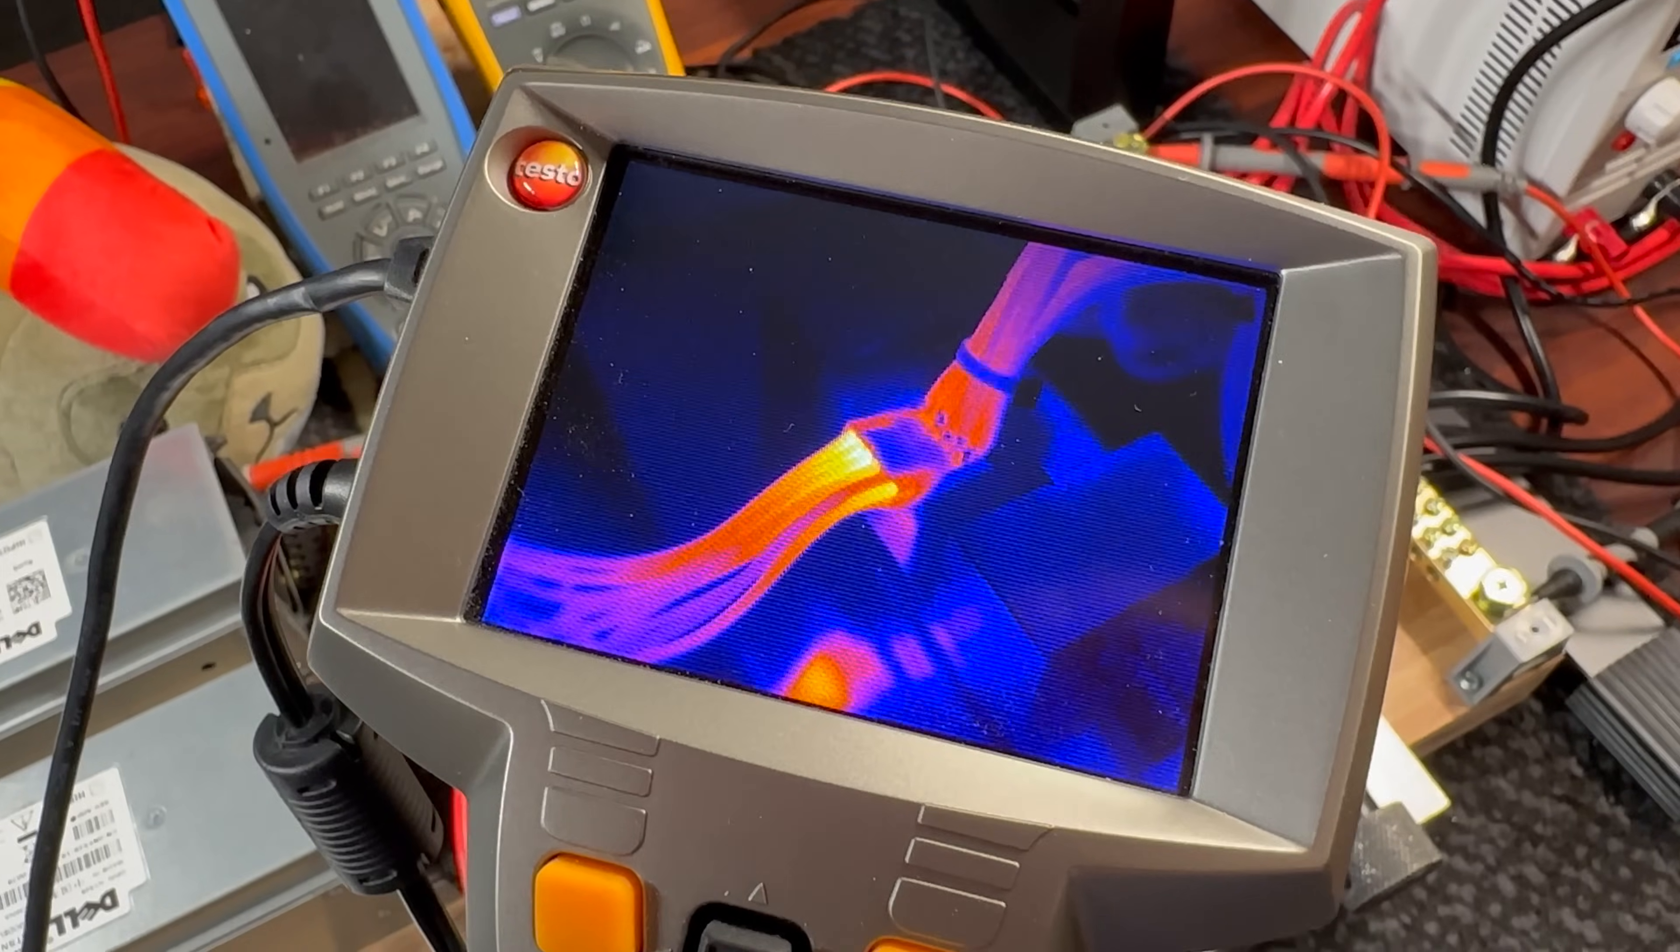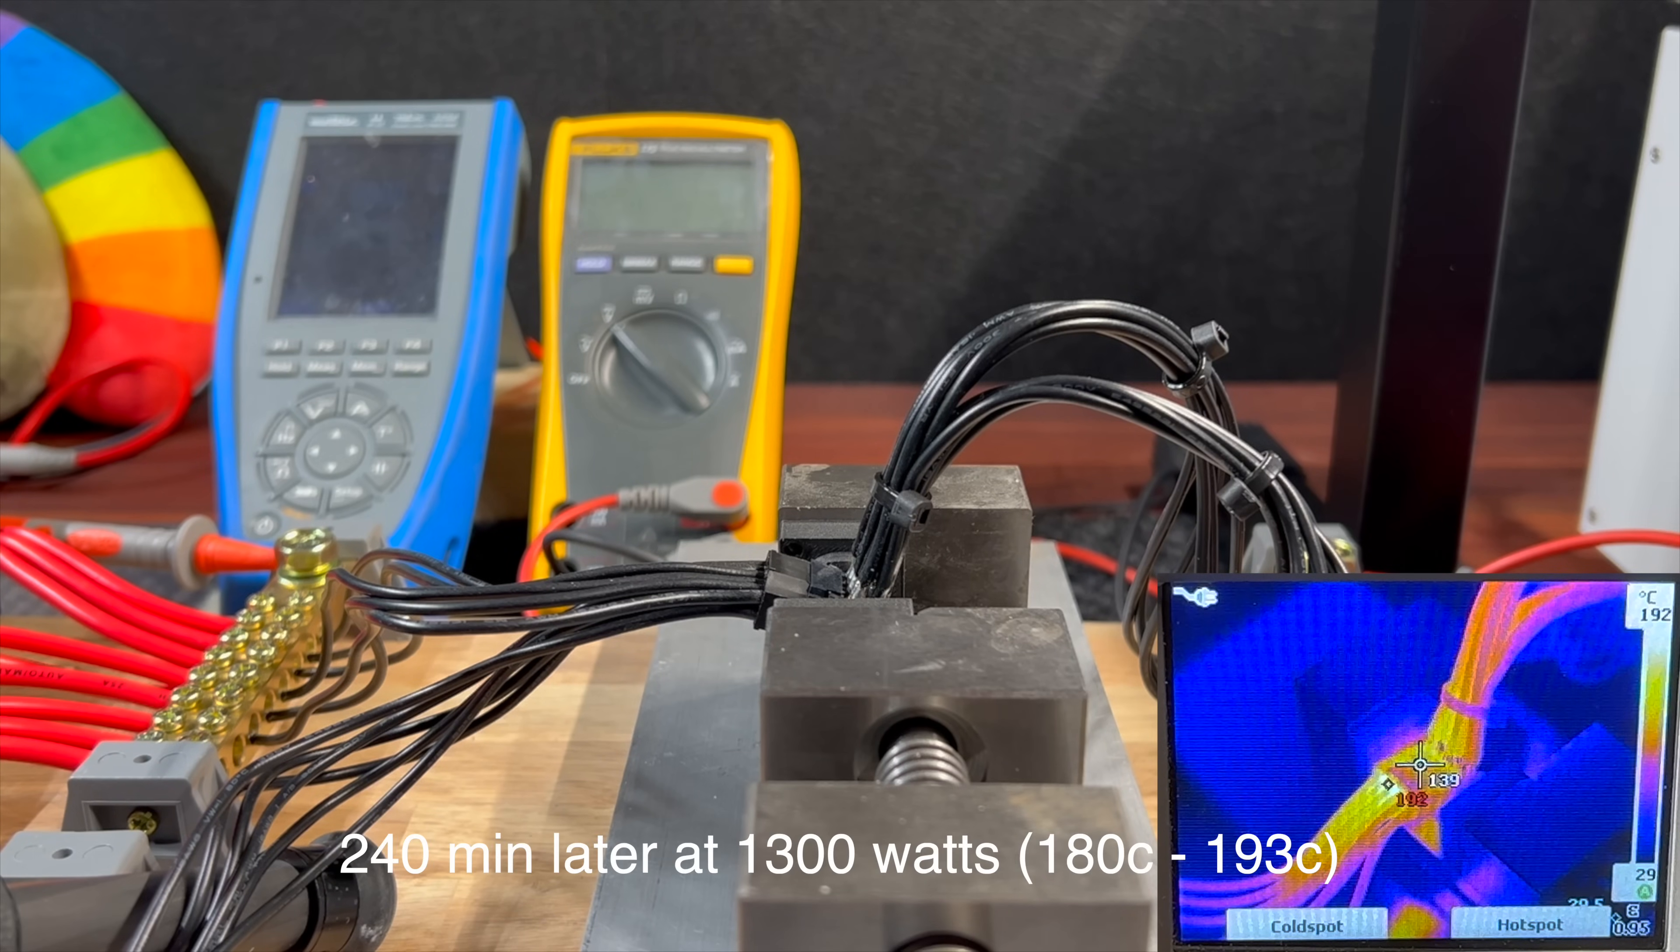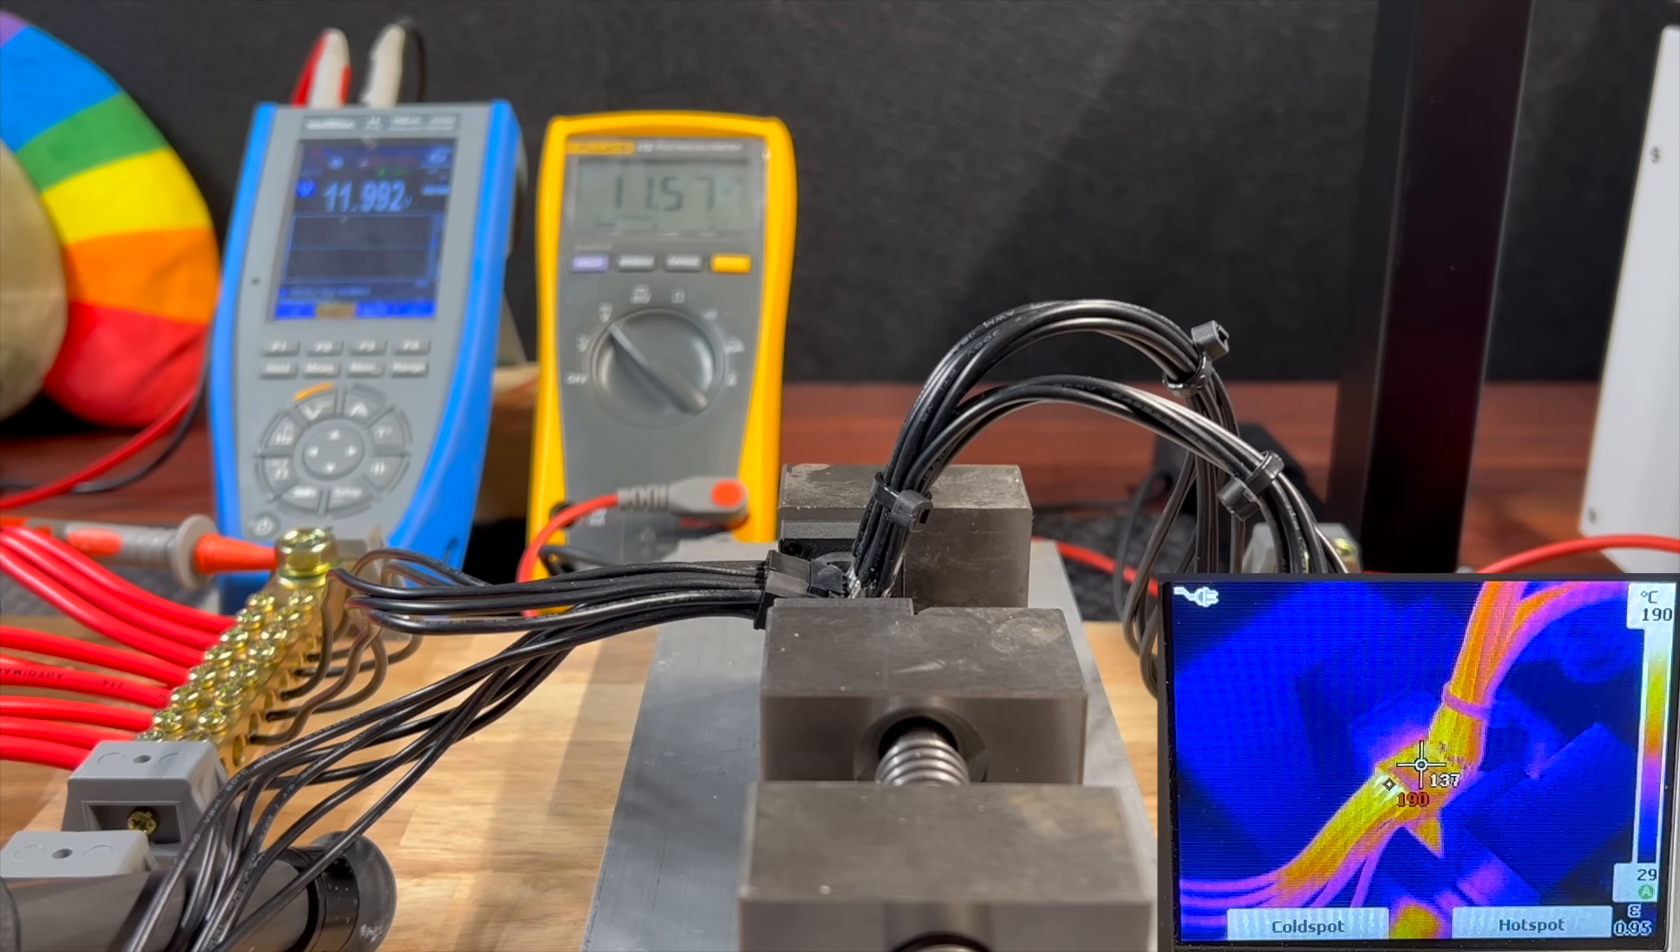Now we're seeing something—that pin that was playing up earlier is doing its thing again. We can see there's no heat on that pin as soon as I applied the load, so those other pins are doing a lot of work compared to that one. I've decided to start filming because something is happening. I'm seeing smoke. The temperature is increasing. I've checked the current across all the wires—it is a little bit different, but the temperature for some unknown reason just keeps increasing. I think we might be starting to see a failure now.